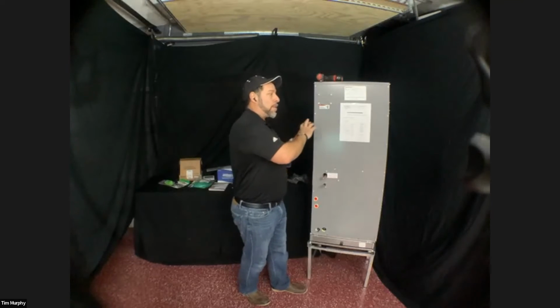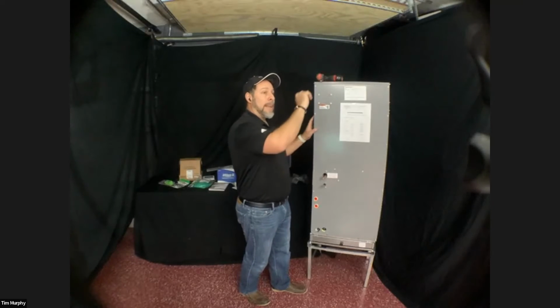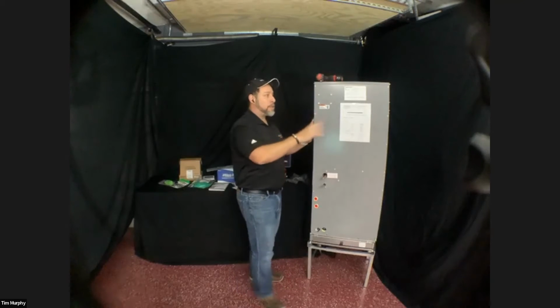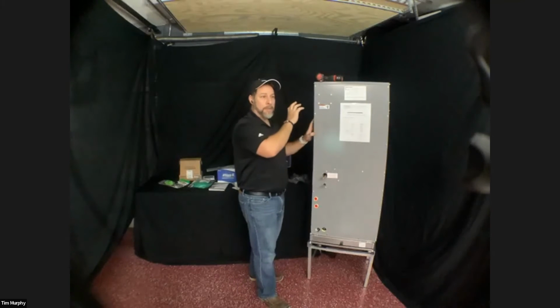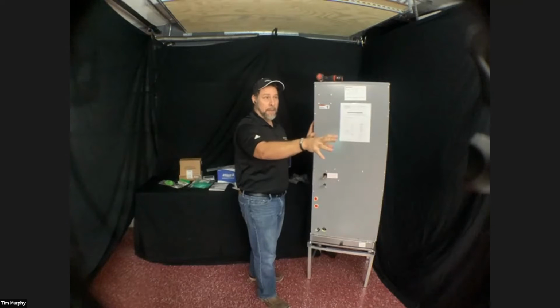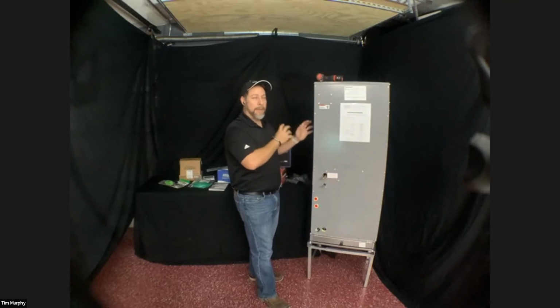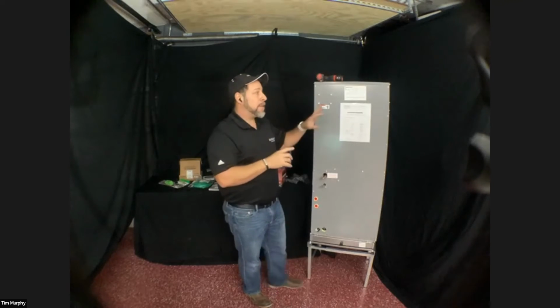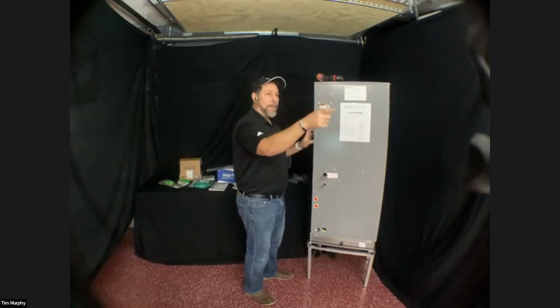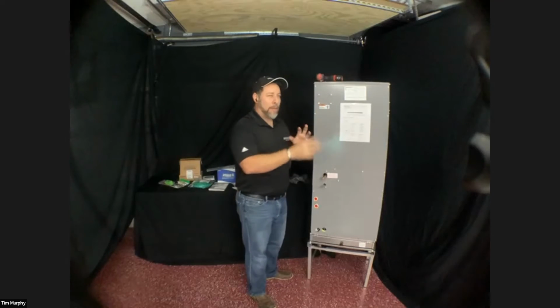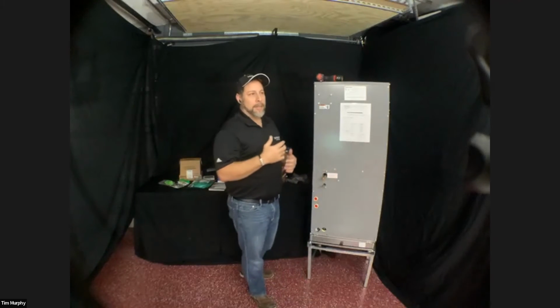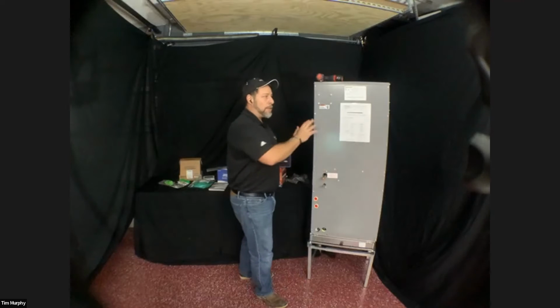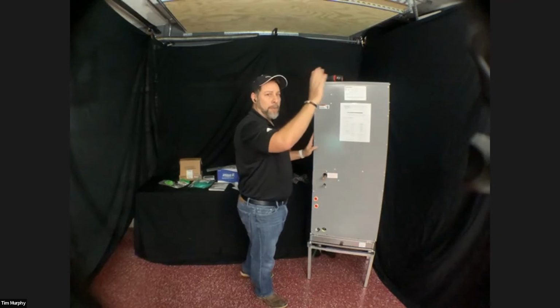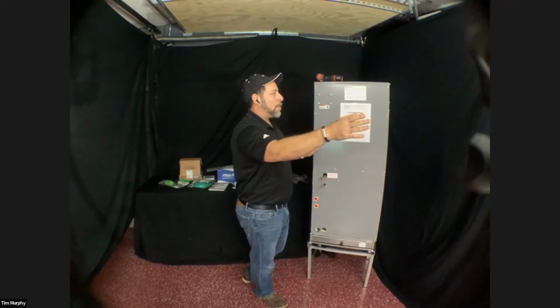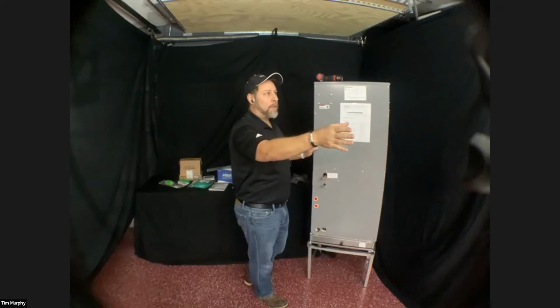So utilizing that, or running that line voltage from the condenser, is going to ensure that the air handler is going to have the same voltage as the condenser, so you're not going to have the possibility of that nuisance call. Also, not to mention, when you run the ground from the condenser to the air handler, that ground plays a role in the communication as well. So that's another reason why you really want to just run the line voltage from the condenser, and then you're going to run your control wire to it as well.